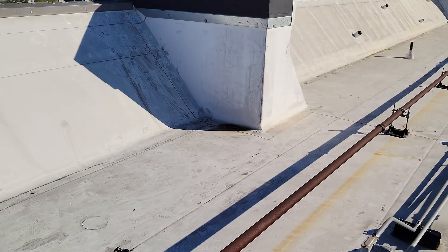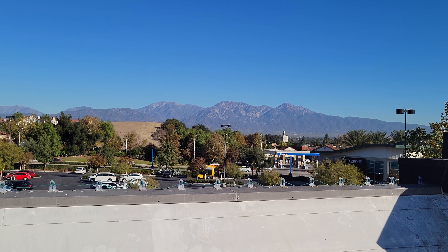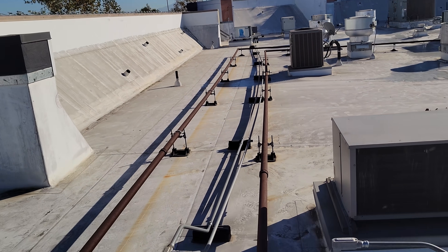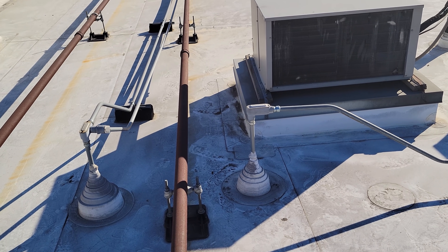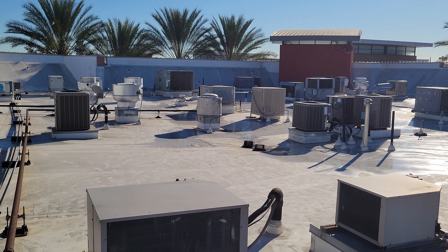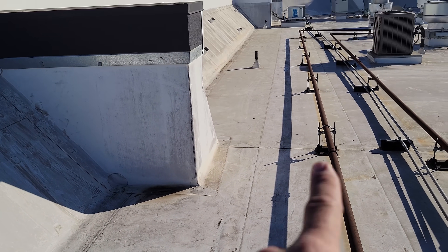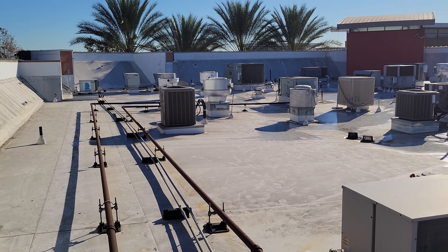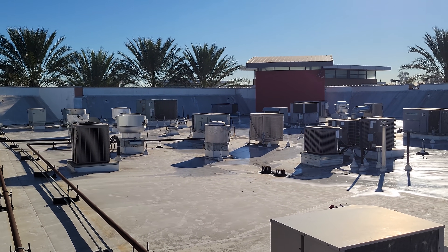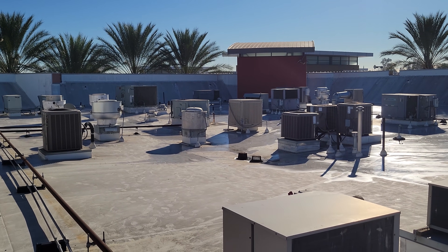I'm back up on the roof — we've got a great view today. Mount San Antonio, Mount Baldy, Rancho Cucamonga-ish area. What I did was downstairs at the walk-in box, I identified what I think is the swamp cooler above the walk-in, and I counted paces to the roof hatch — 30 paces one way and 34 the other — to verify and figure out where the roof penetration needs to happen. They're going to need a roofer to do this because it's a corrugated metal roof underneath, and this is a shopping mall.